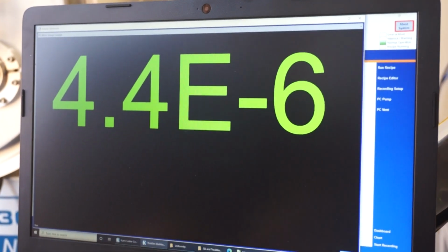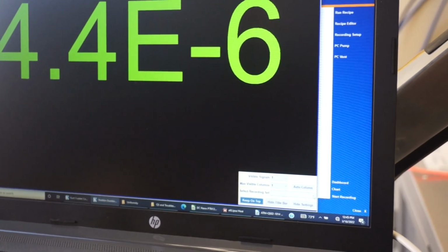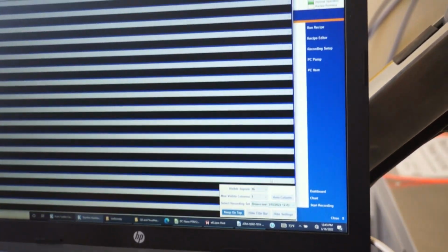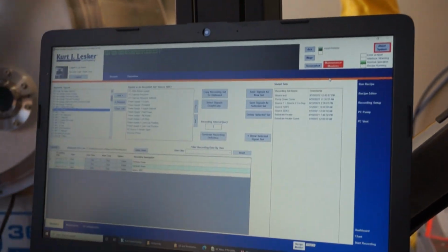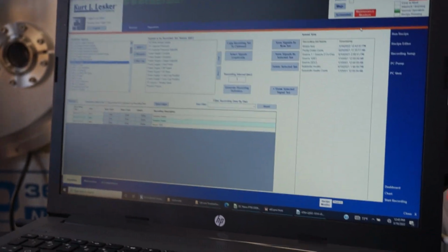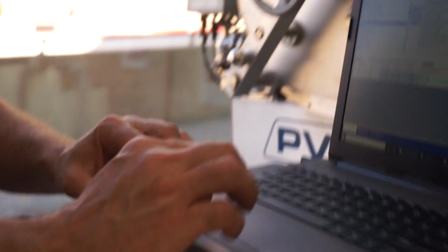But I can go to the settings down here. Now I can go select a recording set. And I can select these, and these are all the things that I just selected. You can show them in the dashboard. You can also do these things, and I have, I think, a 19-page quick start guide that tells you how to set up a chart. You can also show these in the chart. So in the past we've had multiple functionality on how you set up the recording, the charts, and the dashboard. But in reality, if you use the same data set in a table, it's much easier to manage and much easier to understand and train out of. So that's what we like to use.